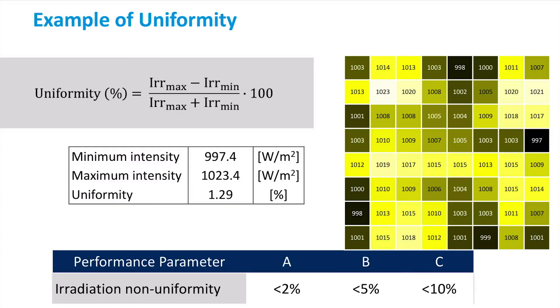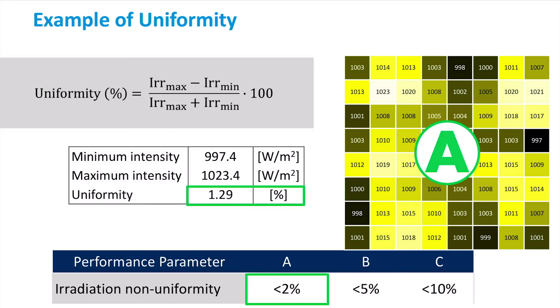In this example, the irradiance was measured in each of the 64 blocks. Then the minimum and maximum intensities, highlighted respectively in black and white in the figure, are used to calculate the uniformity percentage, also called intensity deviation. Here the intensity deviation is 1.29%, which is lower than the 2% threshold. Therefore the simulator can score an A, which is the maximum achievable for this standard.